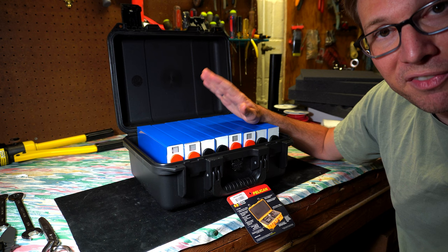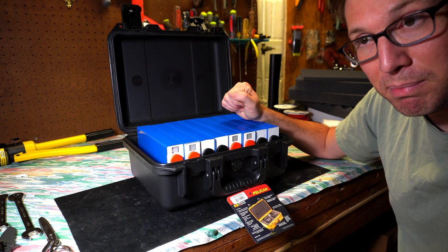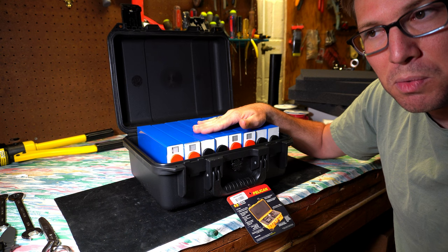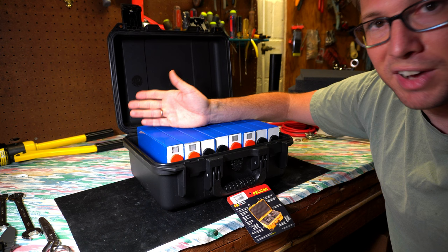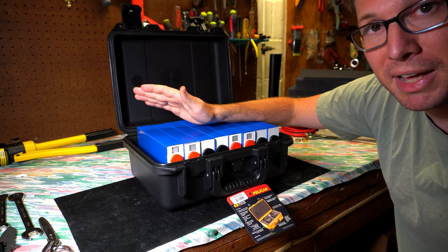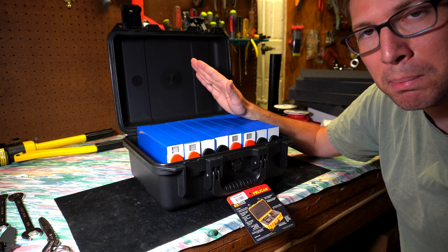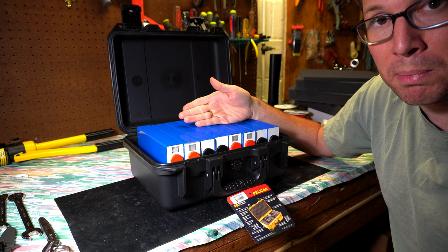If your cells swell, they still work. It's just very dangerous because the next thing they can do is just burst into flames. So that's not very good. A little swelling is okay. It just means that the cell won't last as long as it could have if it were properly compressed. If you compress them well, they'll give you about 5000 cycles. If you don't compress your cells, they'll give you less, like 3 to 4000 cycles, which is still a ton of lifespan. If for whatever reason you can't get the perfect compression on them, it doesn't take much compression. If you can't get the perfect compression, have some and you'll be good enough.